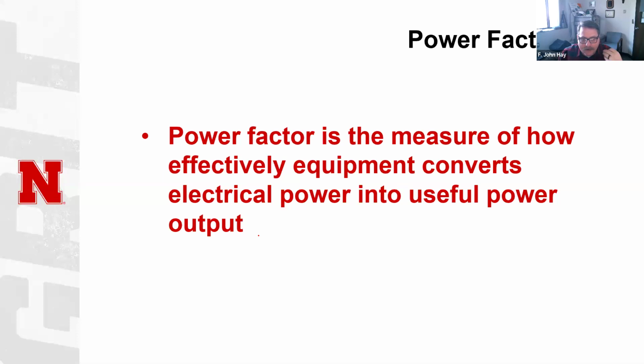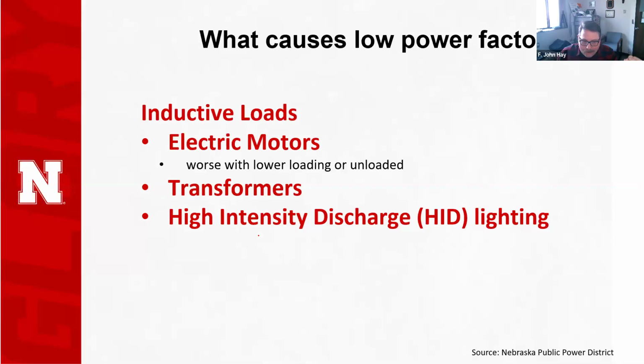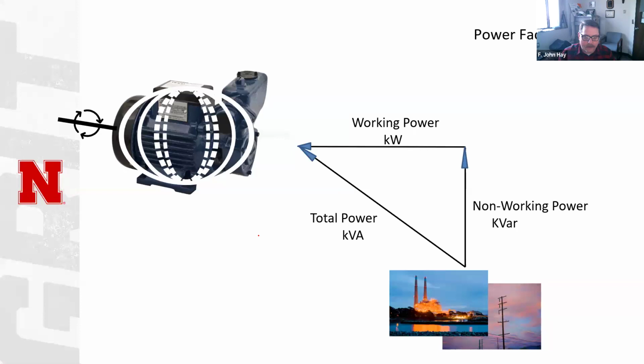Power factor is a measure of how effectively equipment converts electrical power into useful power output. Power factor can be low in inductive loads like electric motors, transformers, and high intensity discharge lighting. Electric motors are what we run into most on farms, and they can cause low power factor, which means some of those costs are now being passed on to the farmer because utilities are measuring them better.